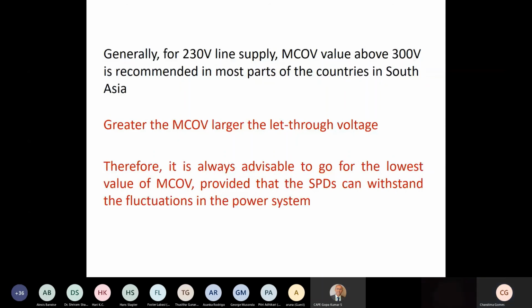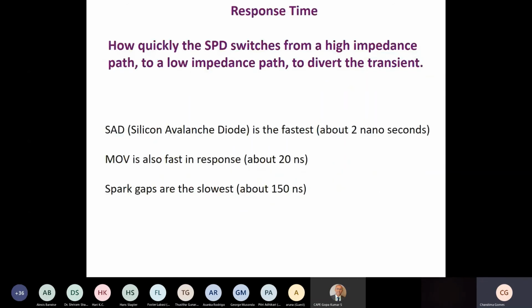But if the power quality in your country is not good, then the SPD may be damaged when you select a low MCOV value. So you better go for a little higher MCOV, but this is very subjective, okay? It depends on the country. Always you better go for low MCOV values as much as possible, but at the same time they can withstand the power quality.